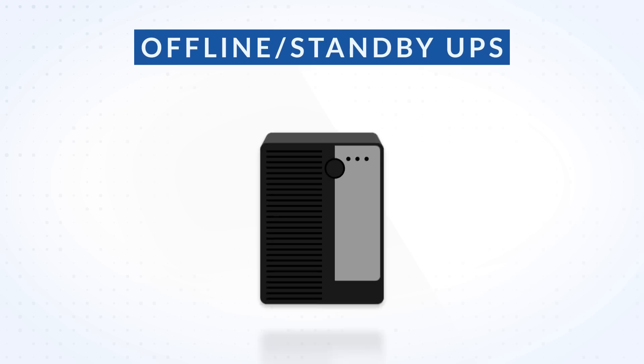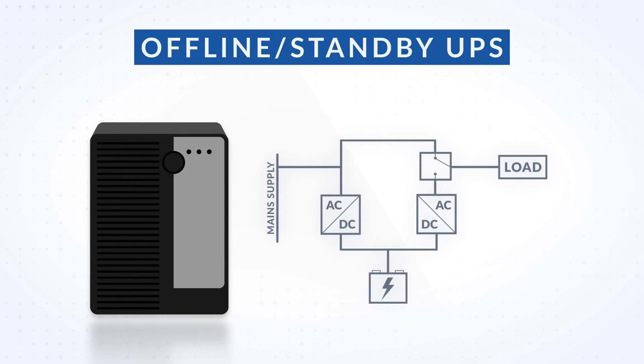The simplest of the three is the Offline, or Standby, UPS. The power from the mains is connected straight to the load and the charger. In the case of mains failure or power fluctuations, the switch changes the supply from mains to the battery.